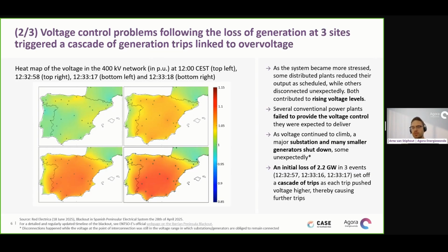Now, at this crucial moment, we have these initial trips, as noted there below, 2.2 gigawatts in 3 events. And this normally, especially the first one, should not be the cause for a system to fail. Transmission systems are designed to deal with failures, but the control measures that were supposed to be there to deal with these voltage issues didn't provide the voltage control that the system operator was planning for. And so as a consequence, the voltage continues to climb.